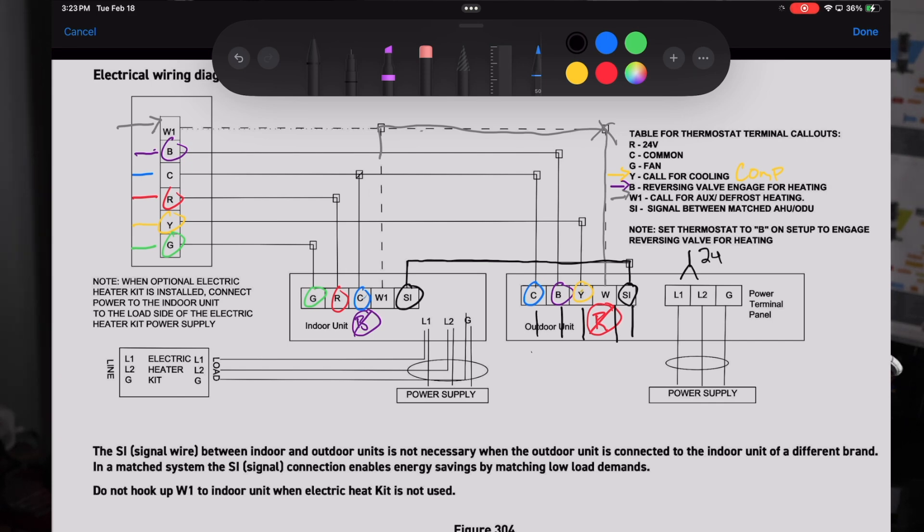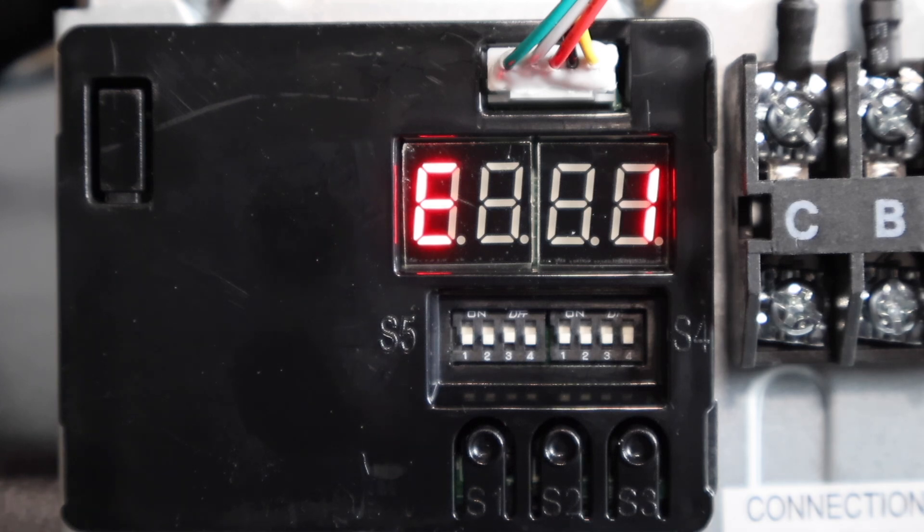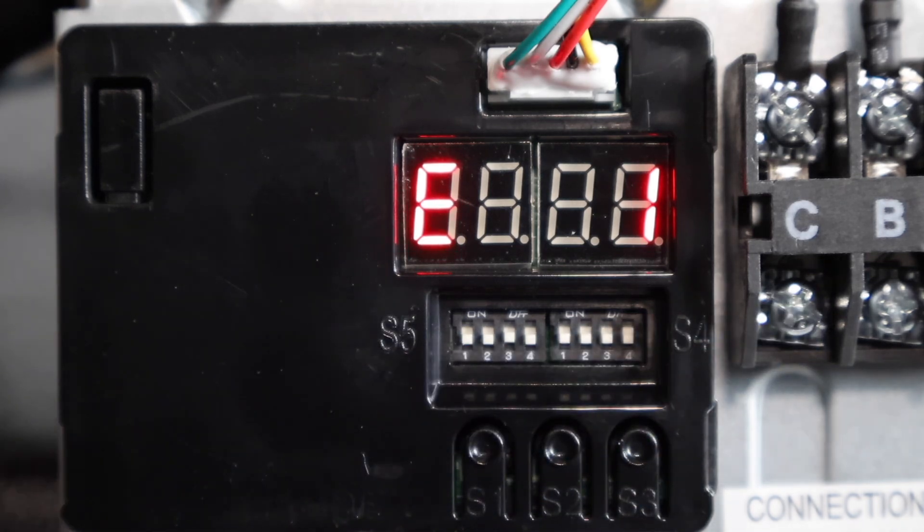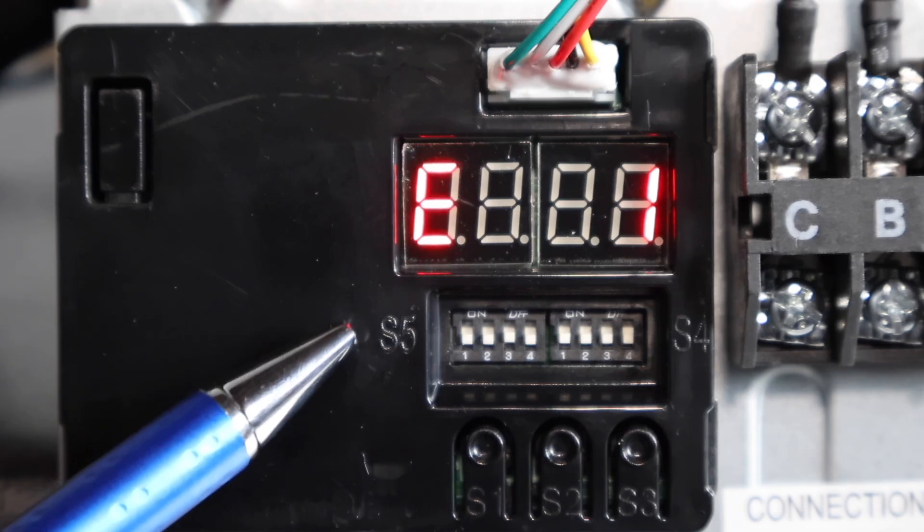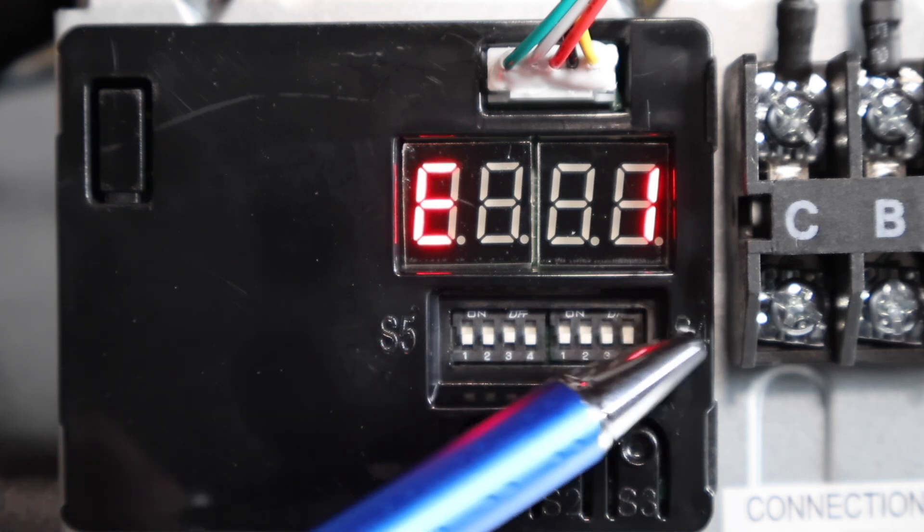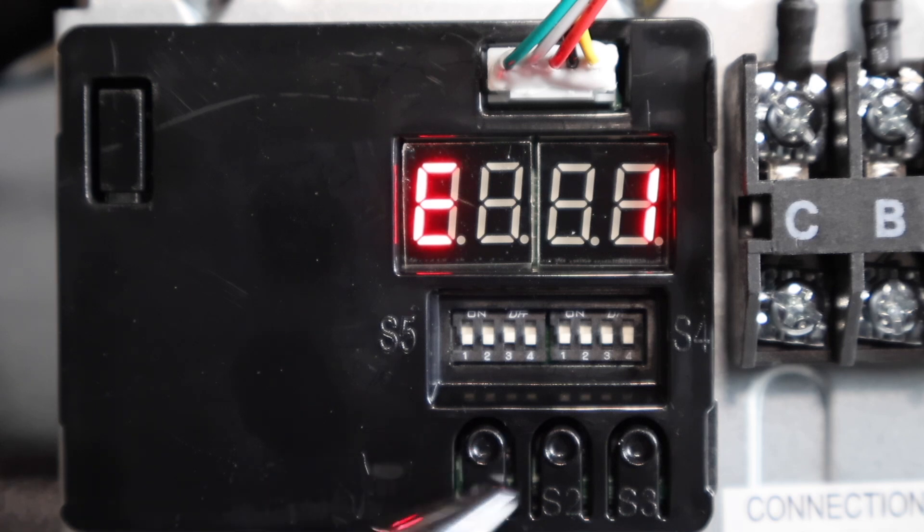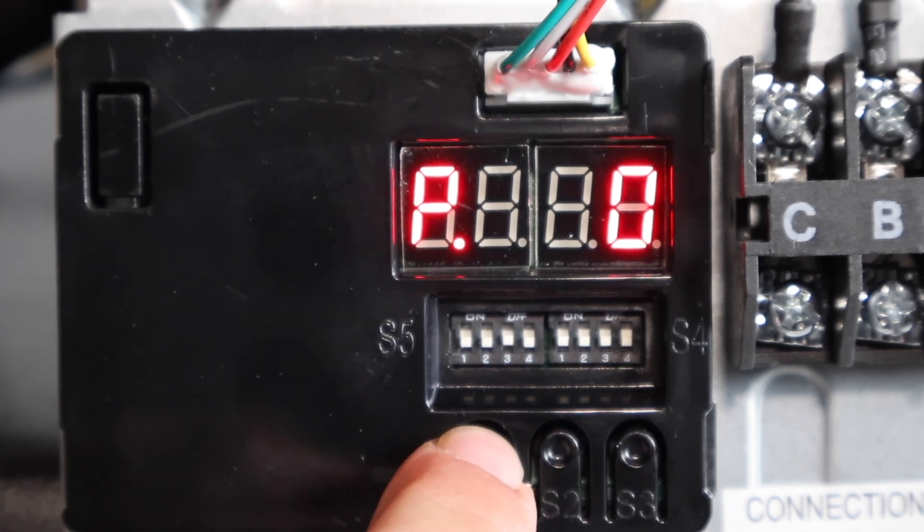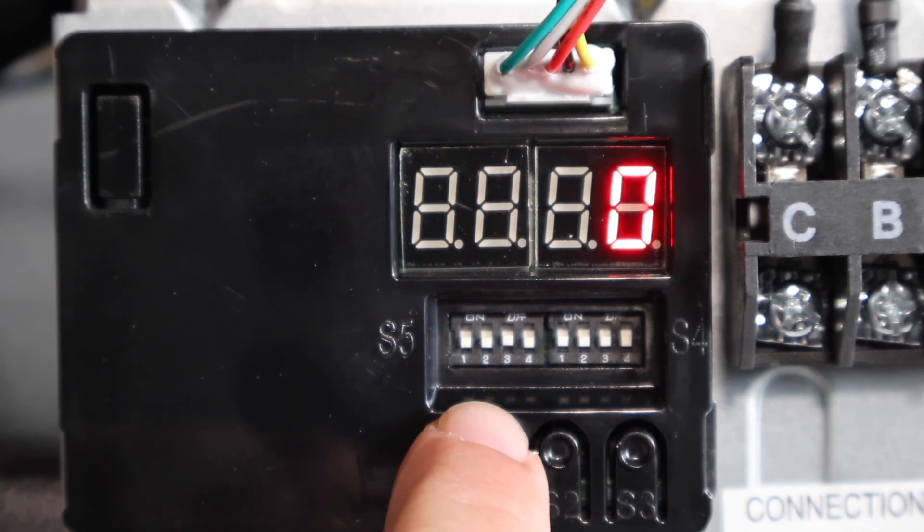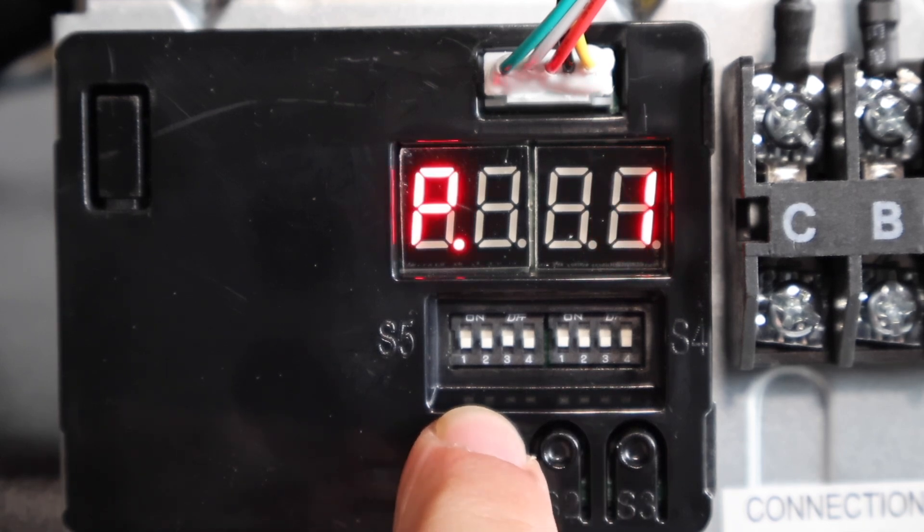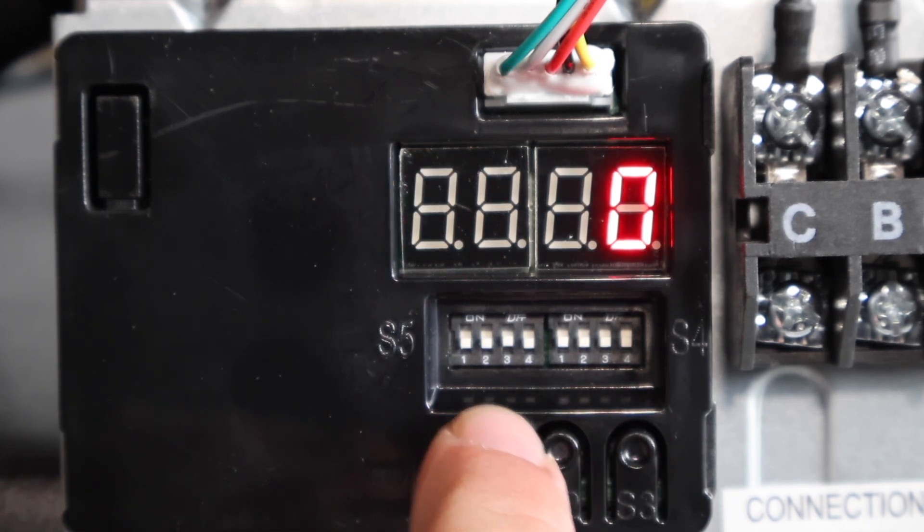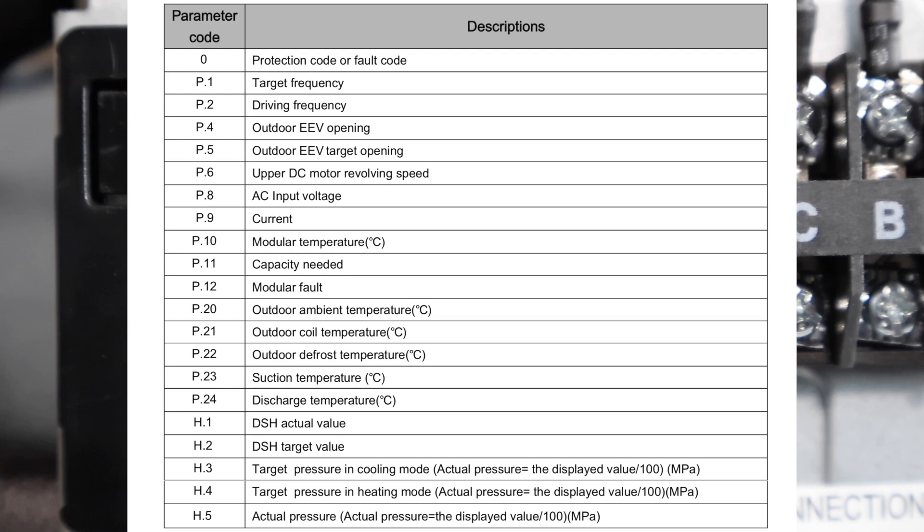And again we covered this a minute ago, but we have our L1 and L2 at the outdoor unit, which is just your 240 volt power coming in. Now that we've covered the low voltage stuff, I wanted to briefly show you what this digital control panel is all about. You have two banks of dip switches here. Make sure you follow the manual if you're going to change anything on these. They don't change a lot but they do change some things. Make sure you also double check and know which switch bank you're on, because switch bank number five is on the left, switch bank number four is on the right. Then you have these three buttons down here at the bottom. Those are to set your parameter code so you can display different things on the unit. For instance if I wanted to see our target frequency for our compressor, I would change that to parameter code one. And obviously right now I'm bench top, I don't have any call for a compressor, so my target frequency is zero.